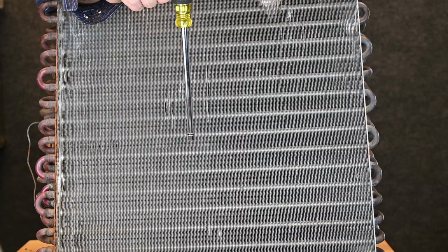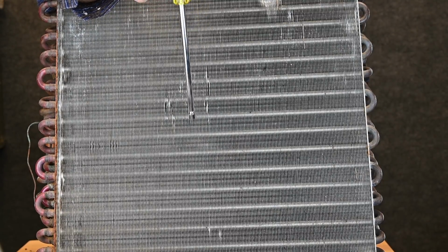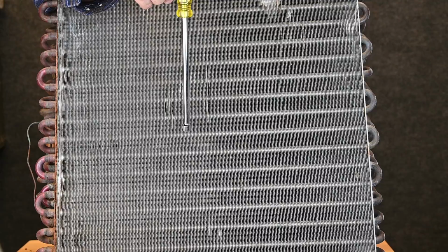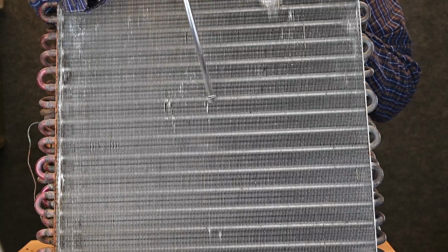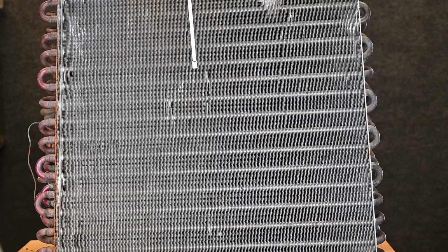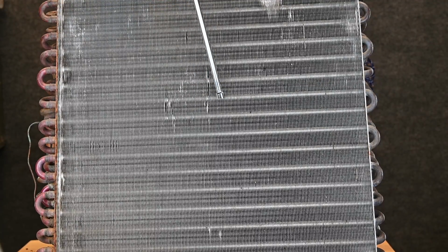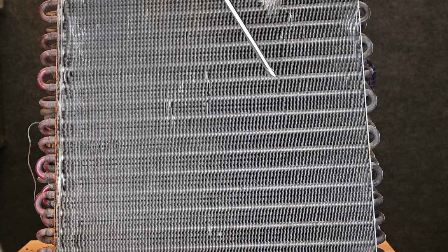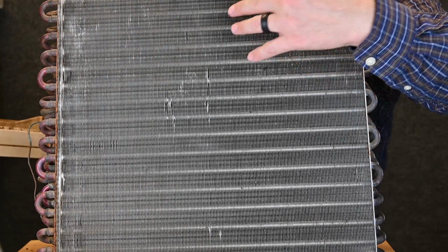On commercial systems, sometimes it's worth it, but for residential units, it's typically never worth it because I have to cut a large hole. In other words, all of this aluminum I have to cut out of the way to get to that tubing on the inside. So even if I'm able to fix that leak in the tubing, I have a huge hole where I'm not having heat transfer. So that's going to be an issue. We talked about that condensate on the inside. It runs down through these fins and into the drain pan.